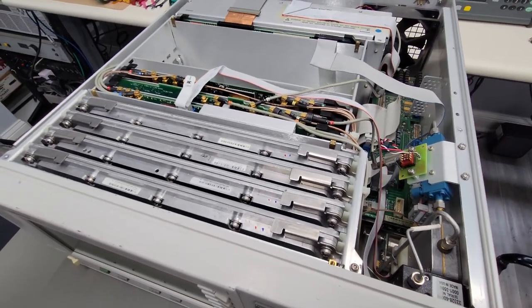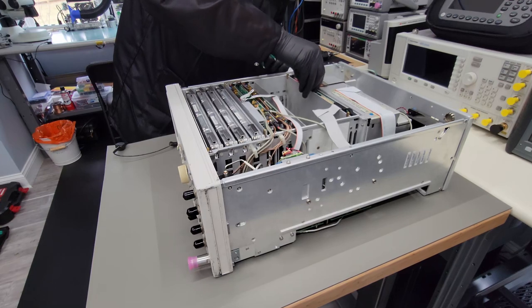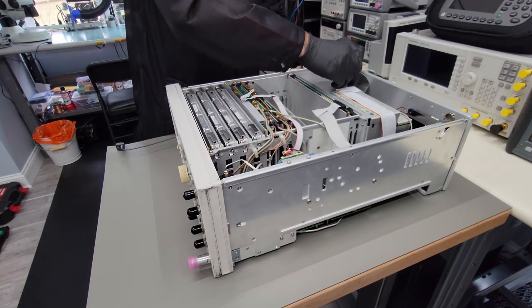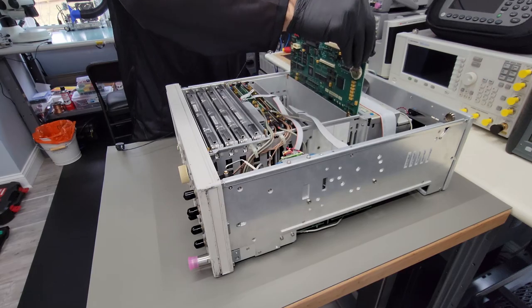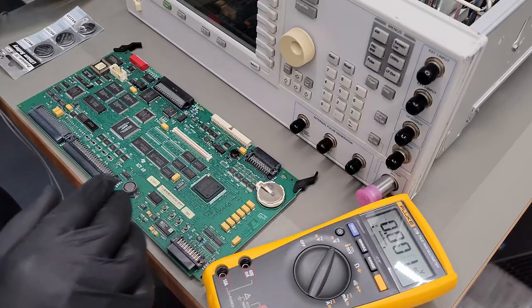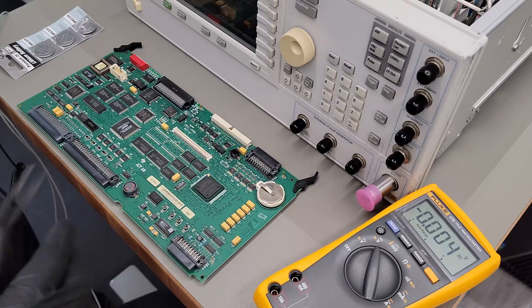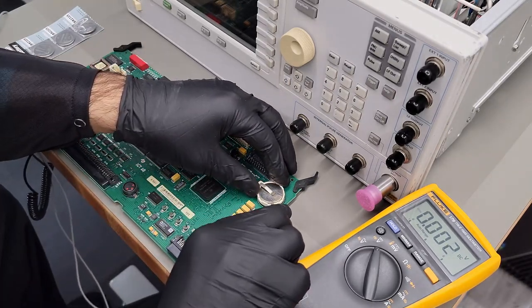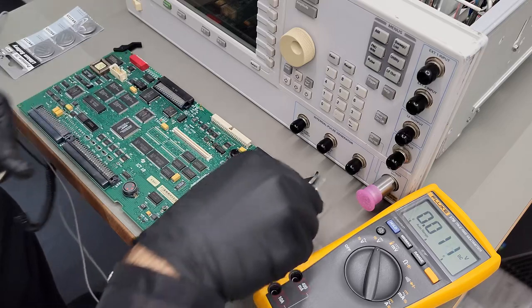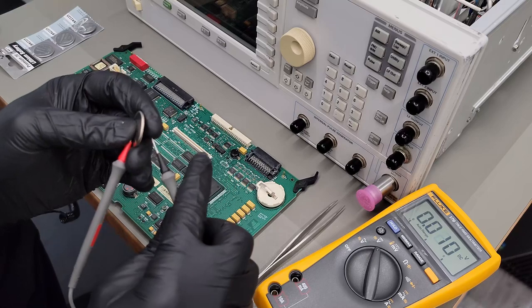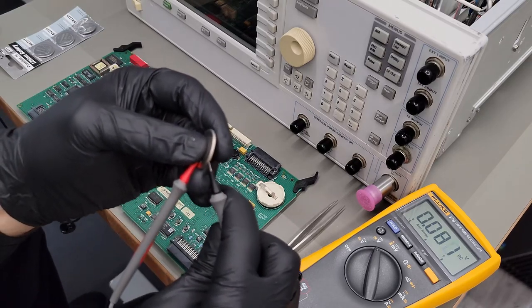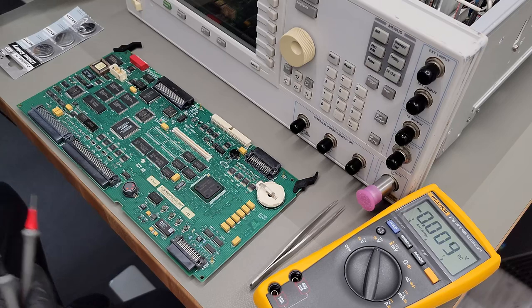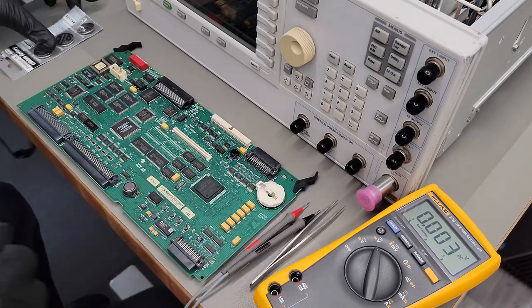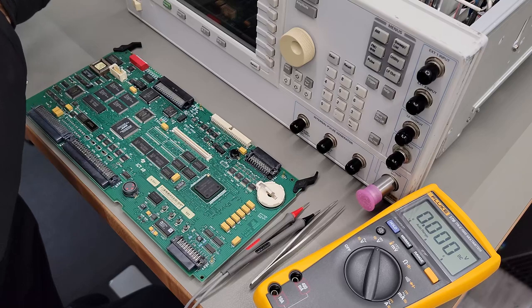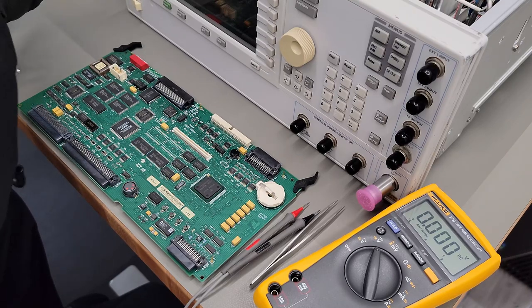So one thing I'm going to do before we get started with the repair work is to replace the internal battery of the instrument. Every time I power cycle the instrument, it does show errors related to file system issues, and those stem, of course, from the internal battery being completely dead. As you can see here, it's pretty much flat. I mean, it's dead. So we're going to throw a fresh battery in there, and that'll avoid some of the extraneous errors that we're seeing every time we turn the instrument on. And it's something that has to be done anyway, so why not just get it over with?